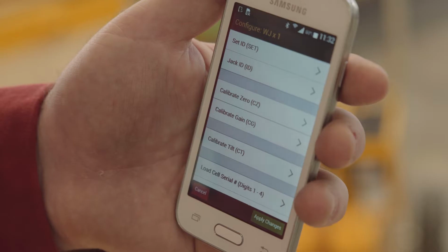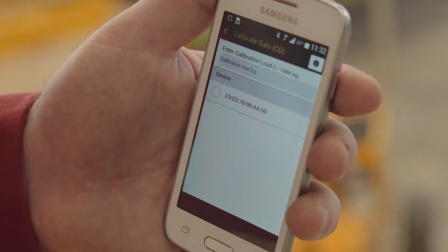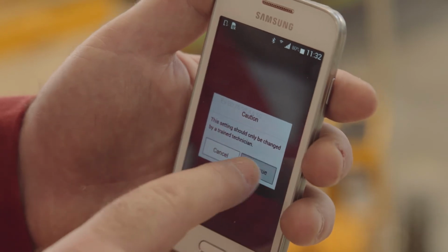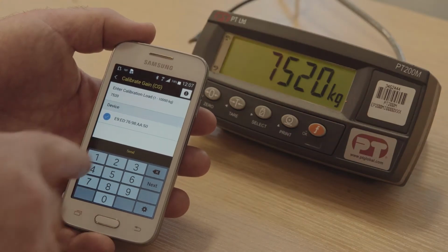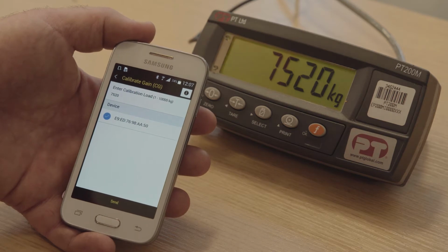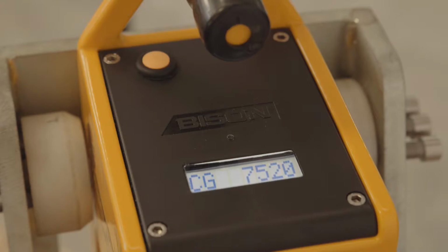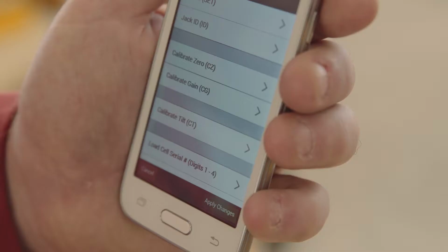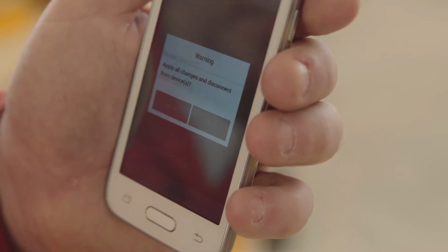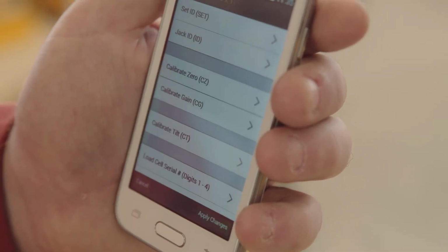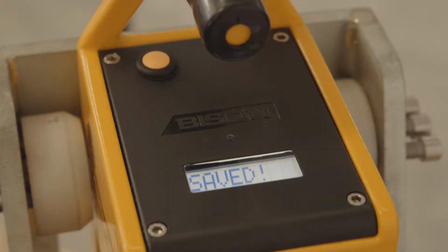Now it's time to calibrate the gain. Select Calibrate Gain from the app menu. Enter the weight value shown on the reference indicator and press Send to pass this number on to the scale. The scale will show CG is set. When you are ready to apply the changes you have made, press the green button on the app. The display will show Saved and then the scale will reboot.